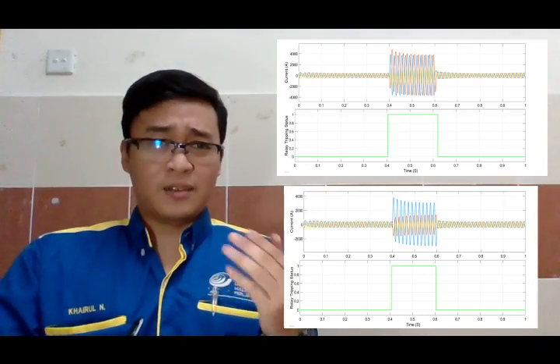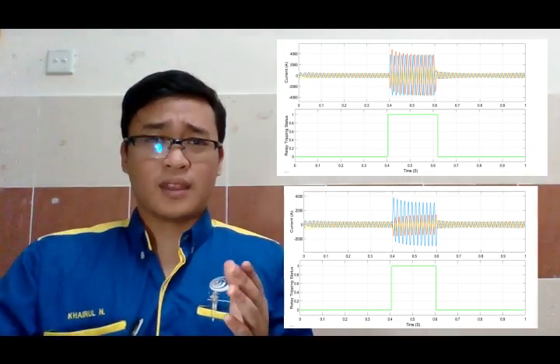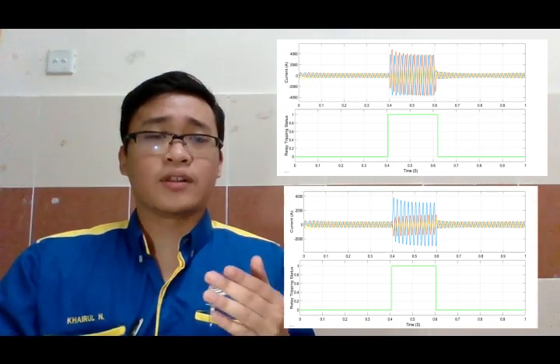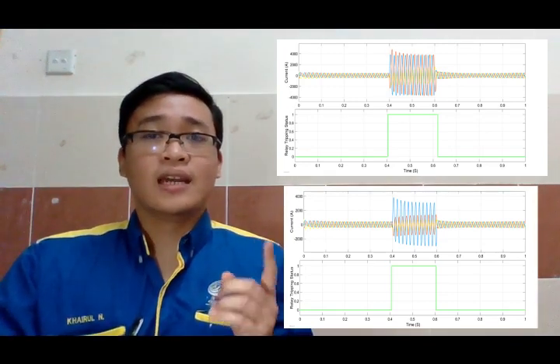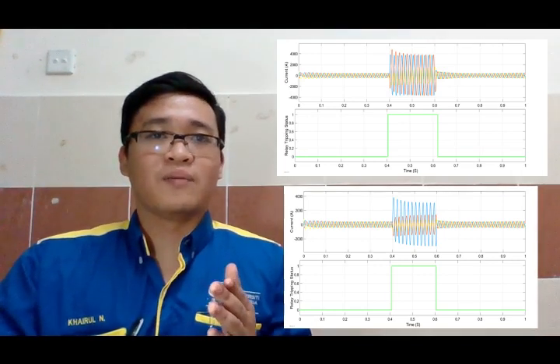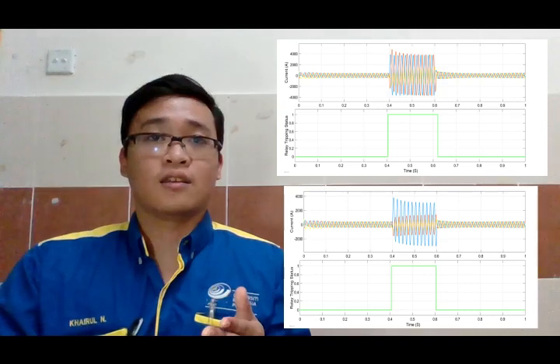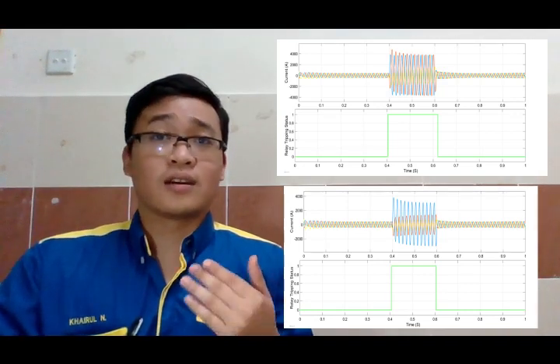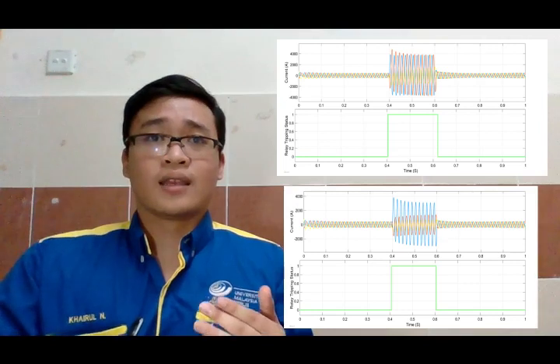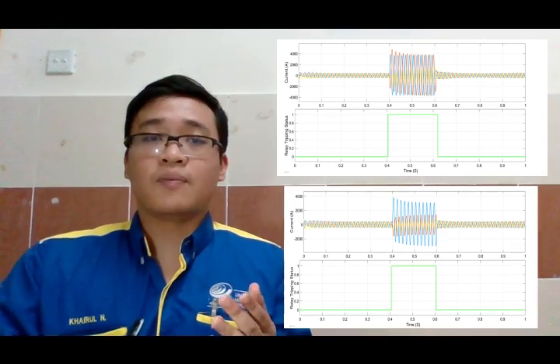Typically, protective relays exhibit sensitivity to current changes. Consequently, in fault scenarios characterized by high resistance, the relay's ability to accurately identify the fault may be compromised due to insufficient current magnitude. This limitation persists even when the fault occurs internally within the protected zone. So in the process of designing the FPGA DDPR, two additional inputs, namely pickup current and slope ratio, are incorporated. By appropriately adjusting these parameters and selecting suitable values for each protection zone, the relay can effectively identify a high impedance fault and initiate a trip action to isolate the faulty section.